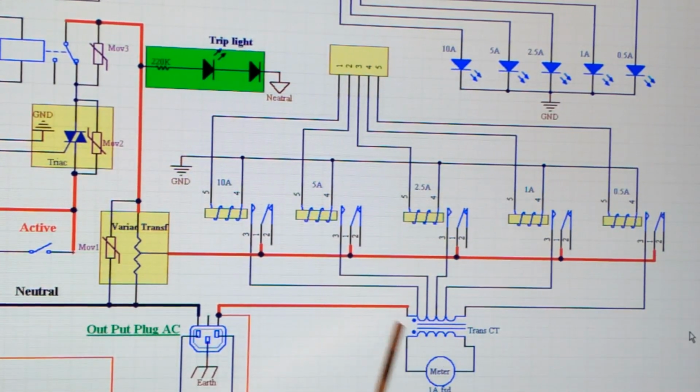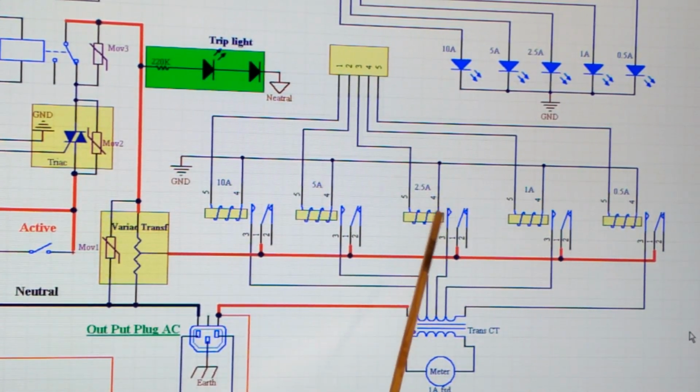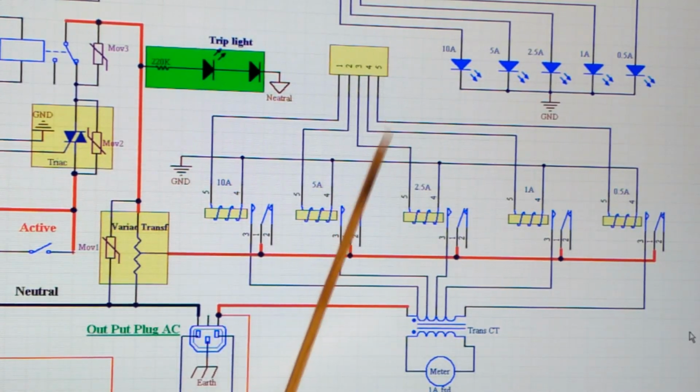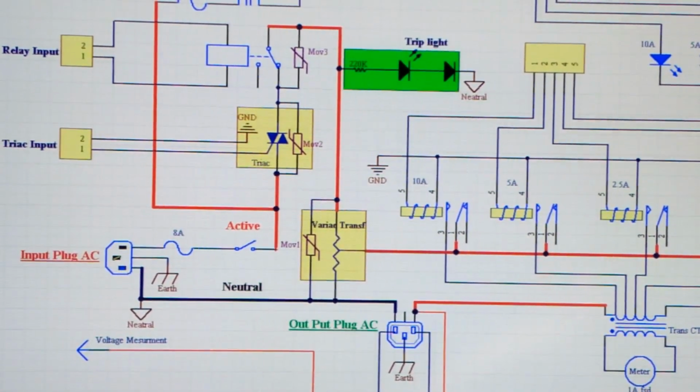That will ensure that you haven't broken your circuit, which means if you don't have that delay and you switch the 2.5 relay off, when the 5 amp meets, it's going to arc because your load is on, and you're going to damage your contacts on the relay. So that's again the explanation behind that.